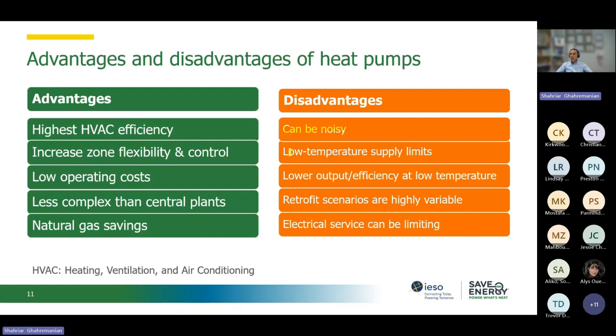There are also low temperature supply limits. When we design or size a heat pump for a facility, we need to consider that. If the temperature is low, meaning it's super cold outside, the output of these heat pumps will be reduced. But again, they won't go much below an efficiency of one - their efficiency stays near one.